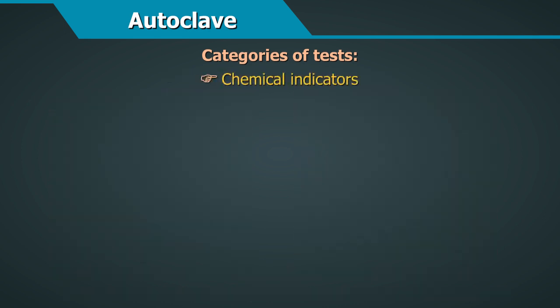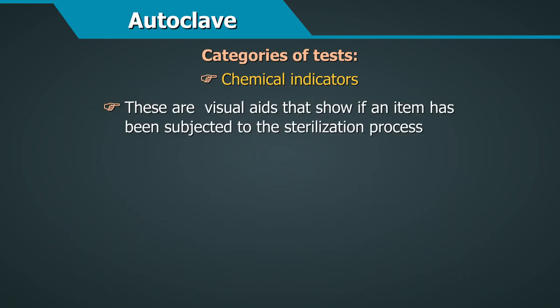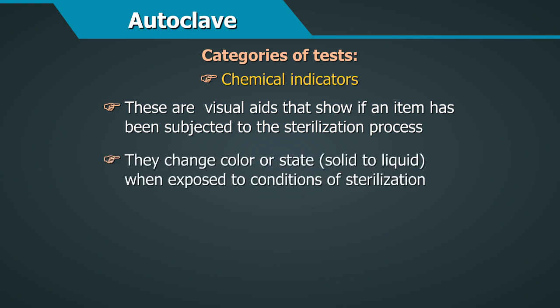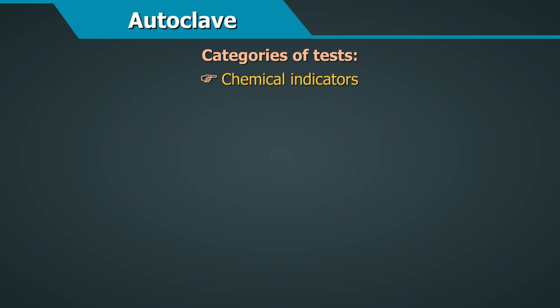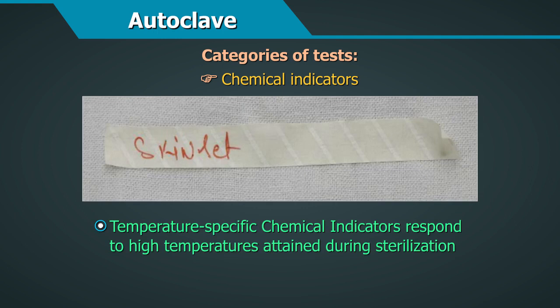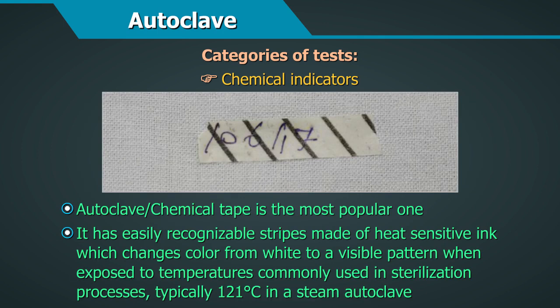Chemical indicators. These are visual aids that show if an item has been subjected to the sterilization process. They change color or state, that is solid state to liquid state, when exposed to conditions of sterilization. Temperature-specific chemical indicators respond to high temperatures attained during sterilization. Autoclave or chemical tape is the most popular one. It has easily recognizable stripes made of heat-sensitive ink, which changes color from white to a visible pattern when exposed to temperatures commonly used in sterilization processes, typically 121 degrees centigrade in a steam autoclave.